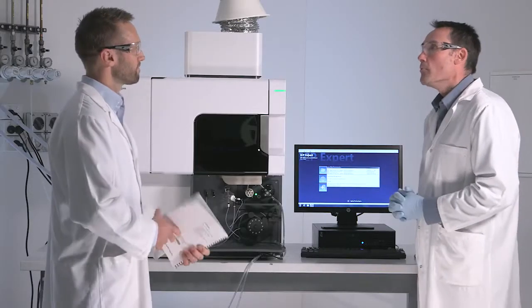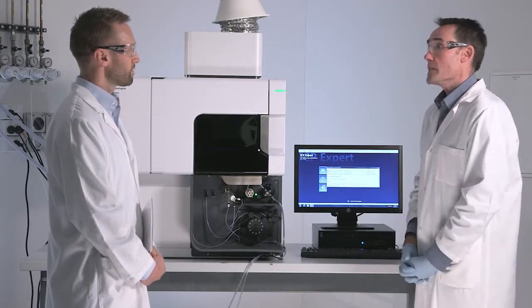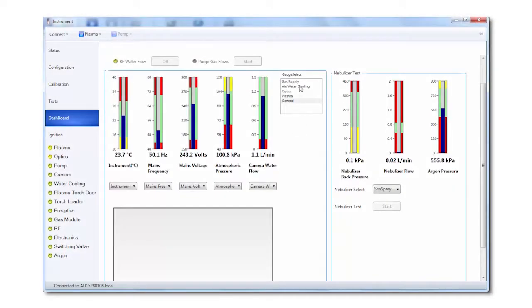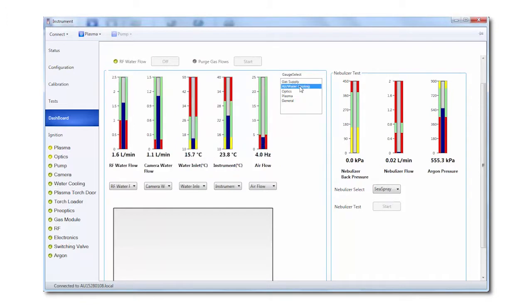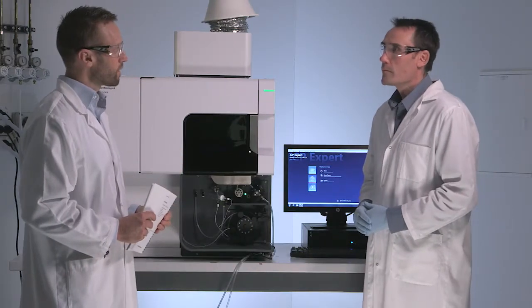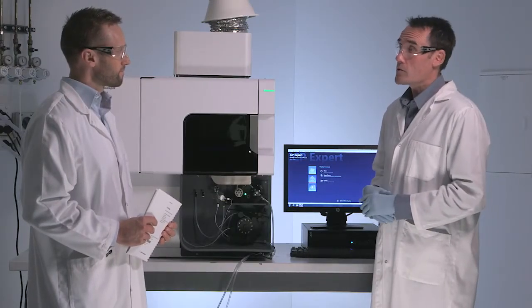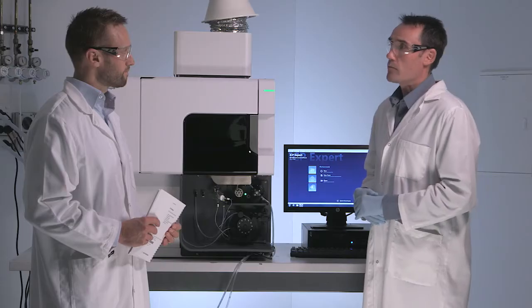Okay, information about airflow also funnels through to the dashboard, so the user can see from a graphical display if there's any problems with airflow or gas supply or chilled water, etc. Ross, can you talk to us about some of the other automated features in the new diagnostic software? So in the diagnostic software, we've added in a lot of additional instrument tests. These instrument tests are automated, and the system will go through a self-check. The information you get back will be displayed on screen, a result for the self-check, and also there'll be a pass or fail to that result.